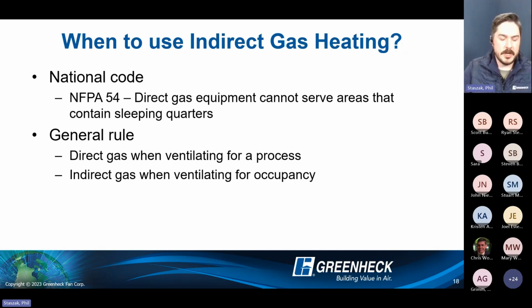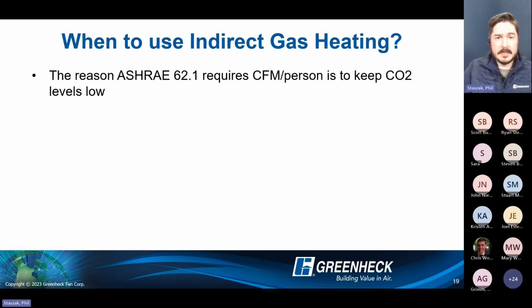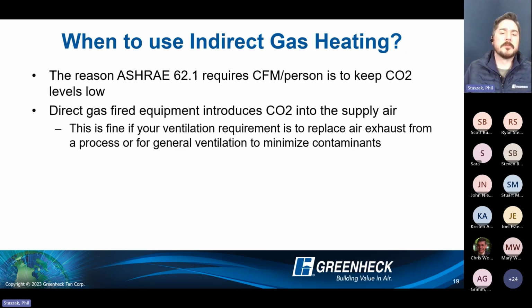But if you need to entertain general makeup air and it is still considered occupancy, shifting toward indirect gas fired does make sense. So the reason why, obviously, is CO2. In ASHRAE 62.1, you need to keep CO2 levels low. And with direct gas fired equipment, it's obviously introducing CO2 right into the supply air. Now, this is where the picture kind of gets confusing, and I think where a lot of people step away from direct gas fired. It's not understanding exactly what those levels of byproducts are and what the process is.